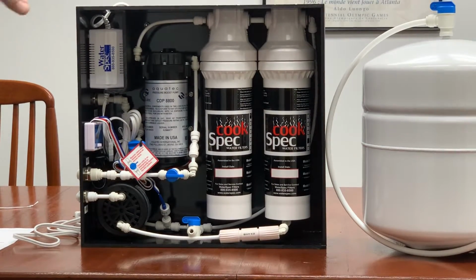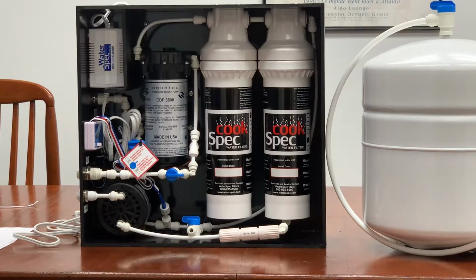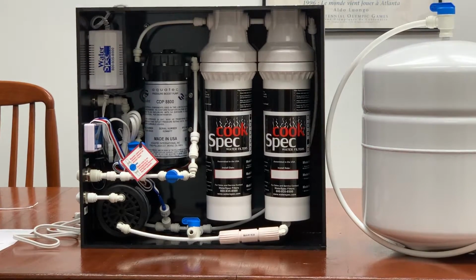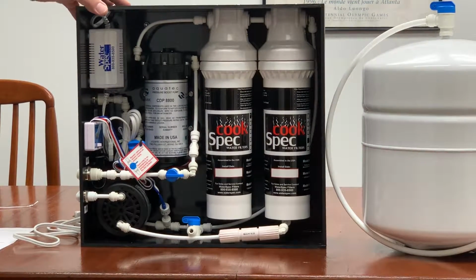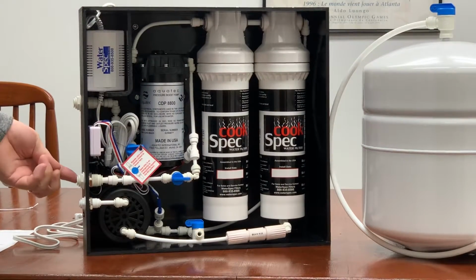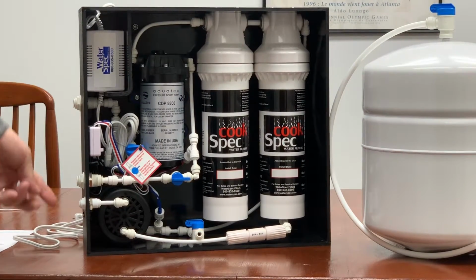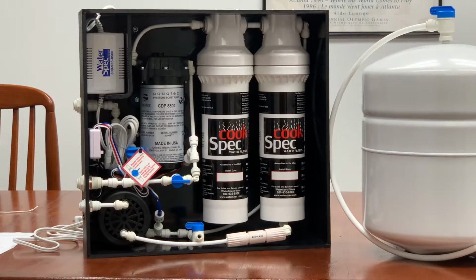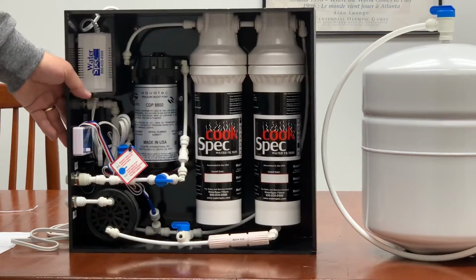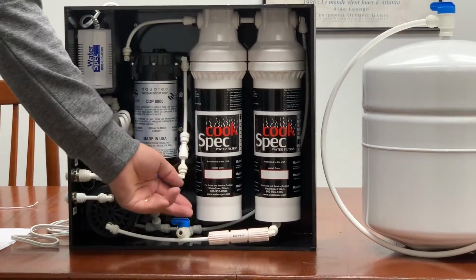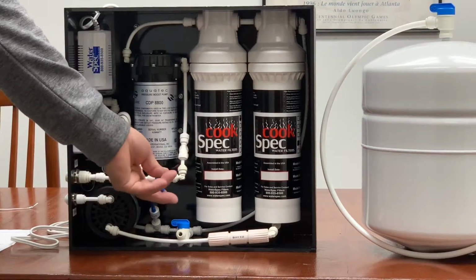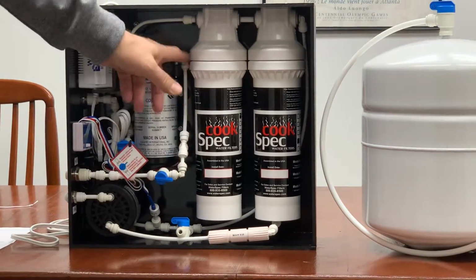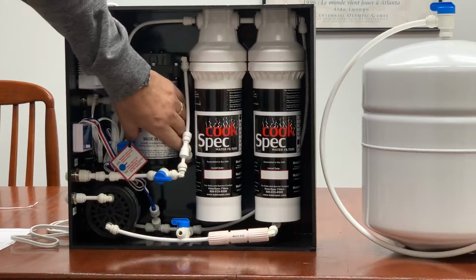Now, first we'll talk a little brief explanation about what the water flow is to the RO and what the components do on this system. First of all, you have an inlet connection, an outlet connection, and a drain line connection. So water is going to come in through the inlet, run to an inlet valve, which can be turned off for servicing. That inlet valve runs up to an inlet side on the booster pump.